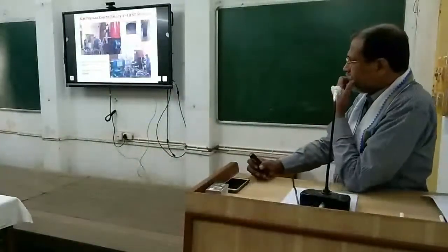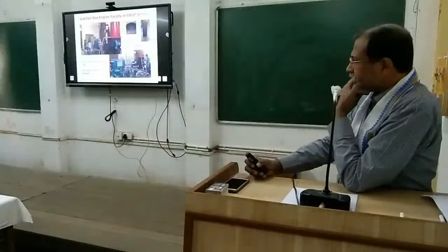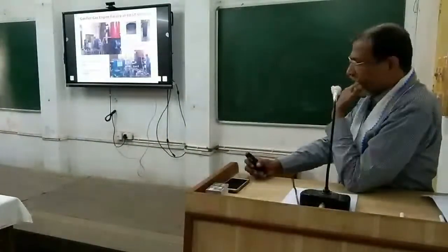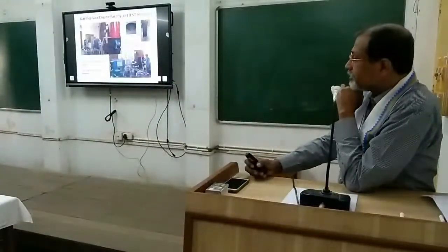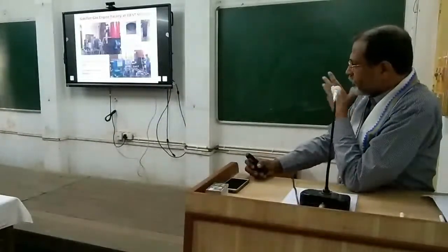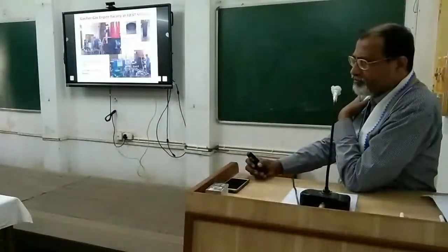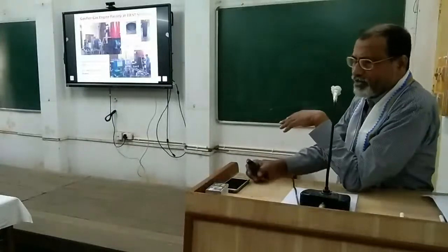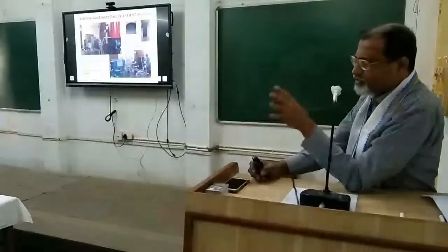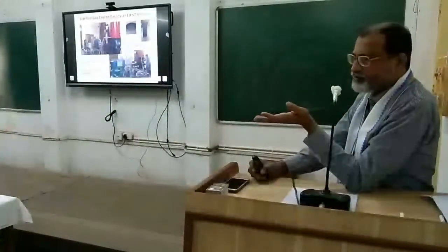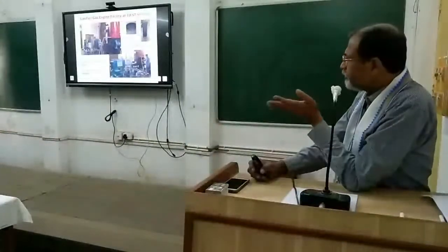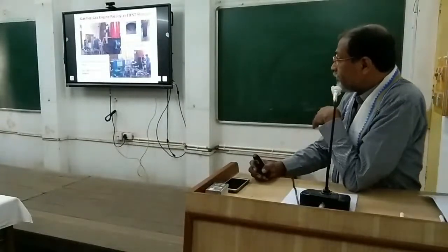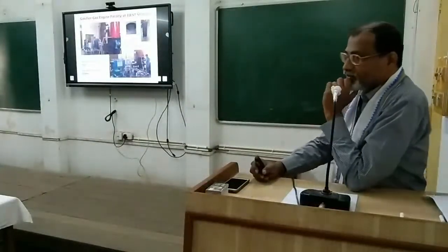Yes, this is the facility we have at IIST. The top left is showing the main reactor. The red one is the gasifier. After the gasifier, whatever you find, all of it is basically meant for cleaning. We have this spray unit for cooling. Then you have these filters, different kinds of filters. We have 3 bed filters. In the second picture you can see the bed filters behind the console panel.